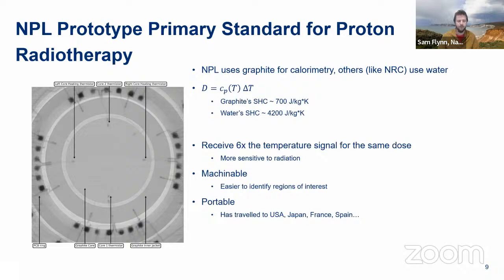The main one is, if you go back to the equation that links dose and temperature rise, the factor that links the two is the specific heat capacity. Graphite's specific heat capacity is about a sixth of that of water, which means for the same amount of radiation dose, you get 6 times as much signal. When you're delivering a clinical radiotherapy dose, say 2 gray, in graphite that will result in a 2.5, maybe 3 millikelvin temperature change, which is very, very small and difficult to measure. And if you want low uncertainty on that, you've got to do it many times. So anything you can do to improve the quality of that measurement is a win for us. That's why we've gone for graphite.